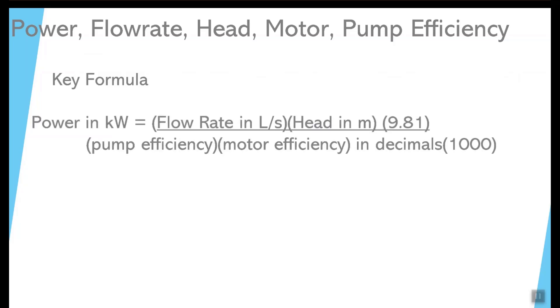Let's take a look at the key formula. Power in kilowatts equals flow rate in liters per second multiplied by the head — that's how much you're going to lift it — multiplied by 9.81. That 9.81 is the same value as in physics: the acceleration of gravity, 9.81 meters per second squared, which takes into account the effect of gravity that the pump has to fight against.